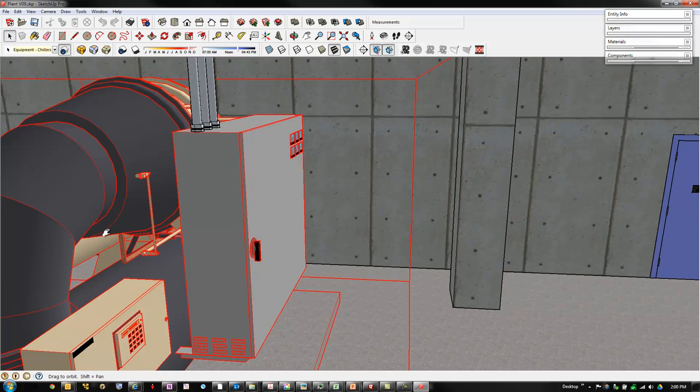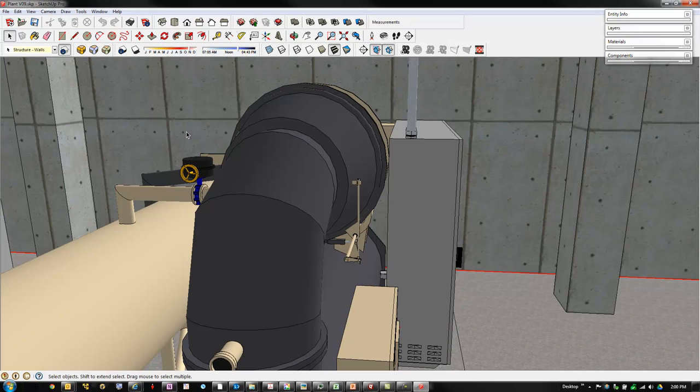All of which gets us back to what this hot gas bypass thing is about. The hot gas bypass, basically this little device right here, false loads the compressor. As you get to the minimum position with the inlet vanes and the machine is on the verge of surging, the control system says, you know what, I've got to keep this chiller running, otherwise I don't make chilled water and I'll start short cycling. And if I short cycle, I'll ruin myself. So I'm going to start letting some hot gas from the condenser bleed into the evaporator. Basically, I'm going to let enough hot gas in so that if I can turn down to, say, 200 tons before I surge, and the real load drops to, say, 150 tons, I'm going to bypass enough hot gas to add an extra 50 tons of load to the machine so the compressor is still doing 200 tons of cooling. Now, you can see right away that's not a very efficient way to operate.